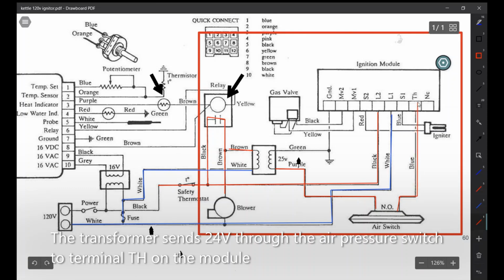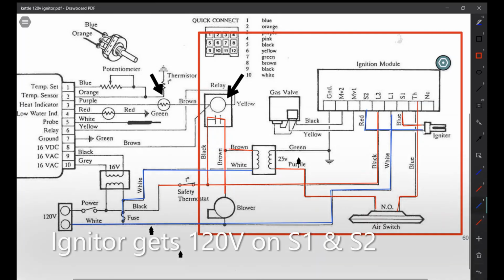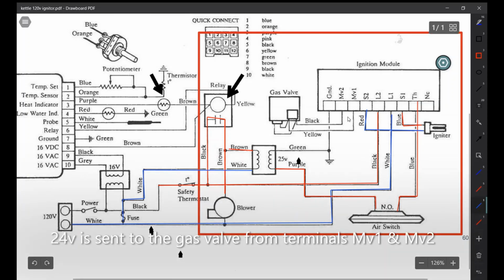Once we get power on TH, it's telling the module to start the sequence of operations for heating. So first thing it's going to do is send 120 volts to the igniter. It's going to send 120 volts to the igniter on terminals S1 and S2. 20 to 40 seconds later, 24 volts is sent to terminals MV2 and MV1, which is going directly to our gas valve. Our gas valve will then open.